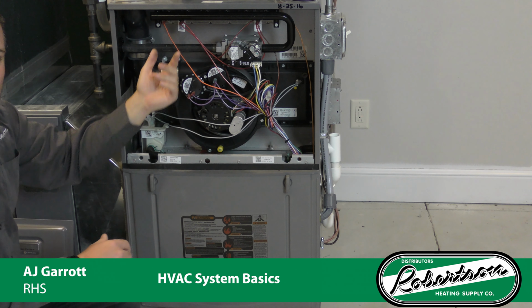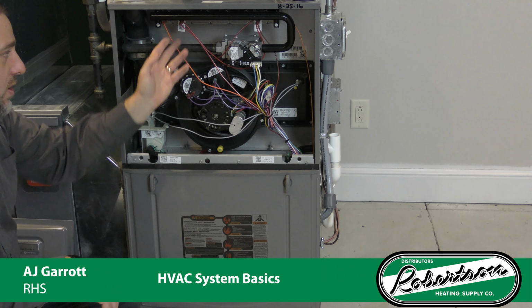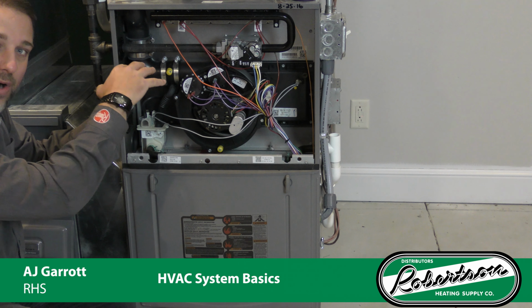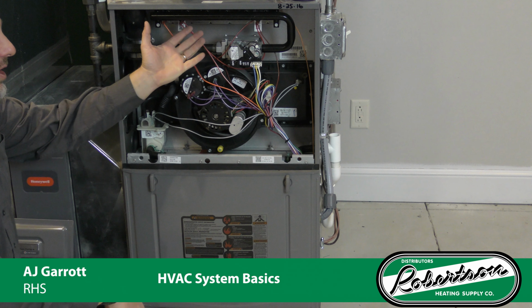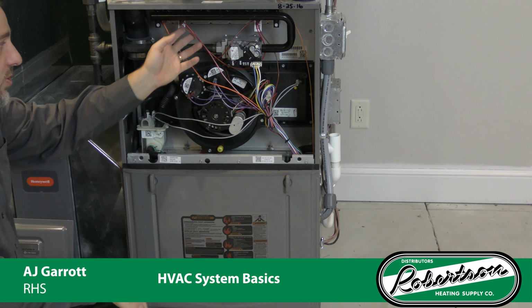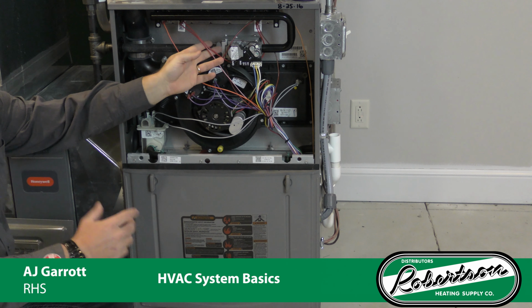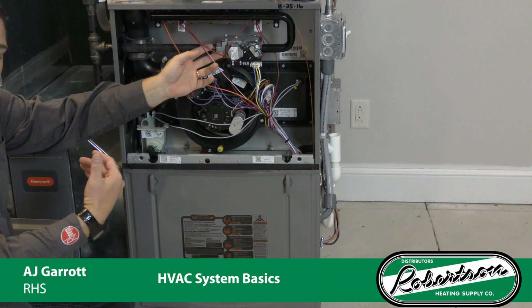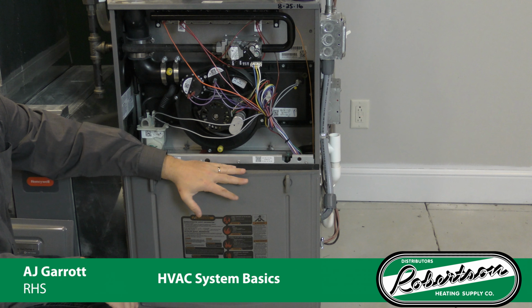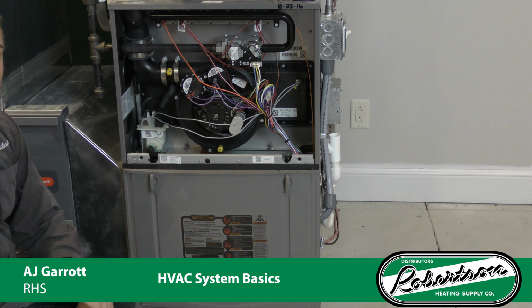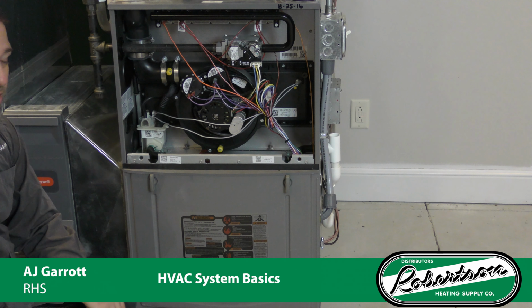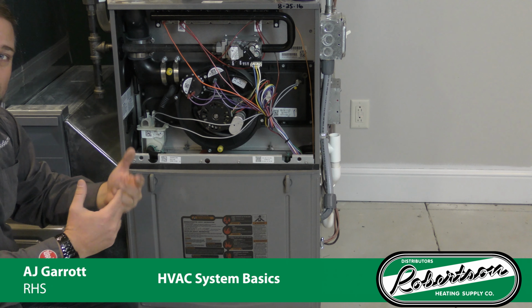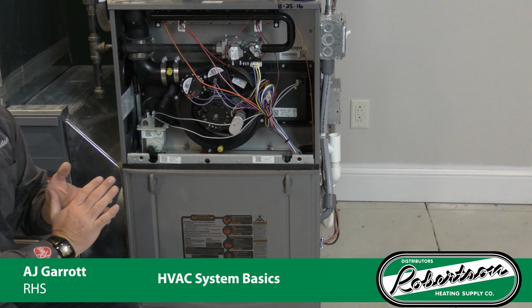Or up here, we actually have rollouts. These rollouts make sure that the flame is shooting properly into the heat exchanger. Should they be rolling back or getting too hot around here, they actually kick and open up and then shut the furnace down permanently. These rollouts are manual resets, so a qualified technician should come out and reset it, but knowing there is something more wrong if one of those set.